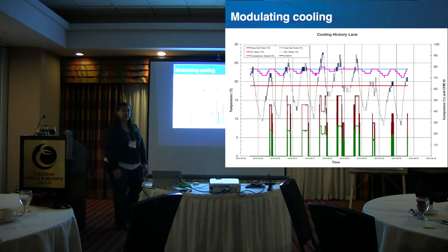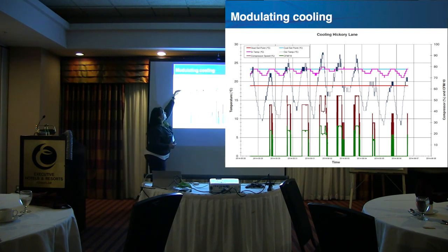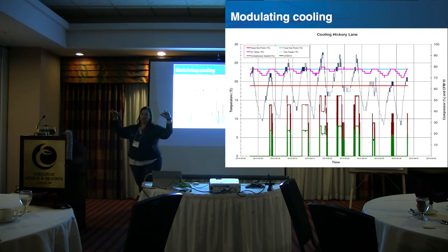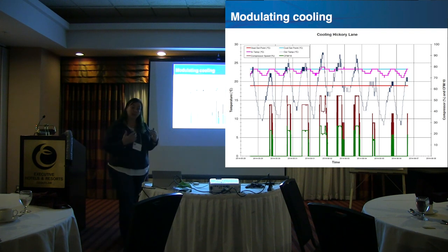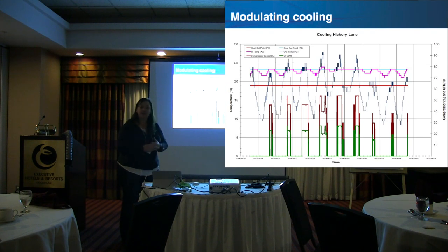And same thing we'll see in heating and cooling. So you've got heat set point, cooling set point, CFM, nothing's running over 300 CFM. The Chinook furnaces will run no higher than 350, but generally we see 300 CFM. No higher than 60% of its capacity, so you can see it running no higher than that. Outdoor temperature, the blue line's all over the place. And then what we want to see is 12 days of nice, consistent indoor temperature throughout that time.